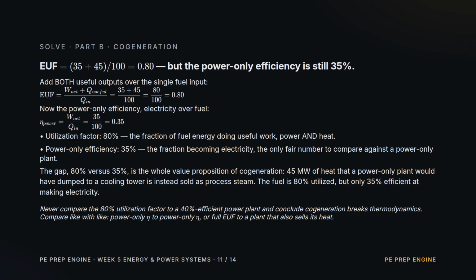Now the power-only efficiency, electricity over fuel, 35 over 100, just 35%. The utilization factor of 80% is the fraction of fuel doing useful work, power and heat together. The power-only 35% is the only fair number to set against a power-only plant. That gap is the entire value of cogeneration. 45 megawatts of heat a normal plant would dump to a cooling tower is sold here as process steam. The fuel is 80% utilized, but only 35% efficient at making electricity. Never compare the 80 to a 40% power plant and claim cogeneration breaks thermodynamics.